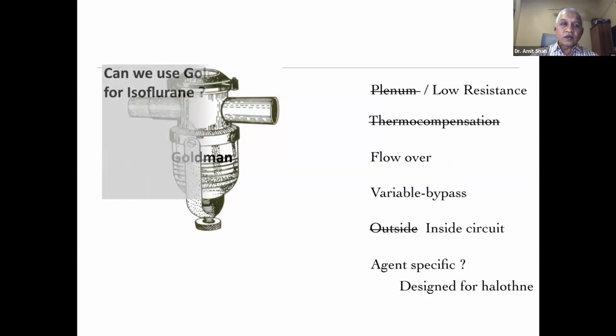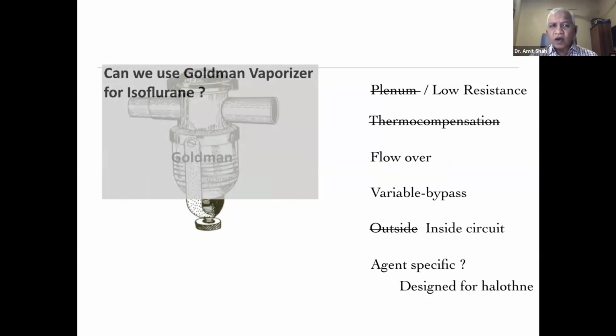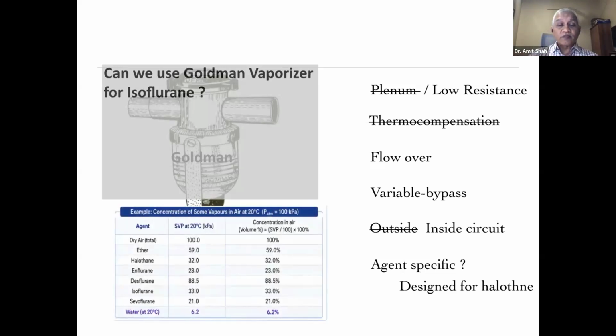Okay. So can we use it for isoflurane? Those who have worked in private practice in the older times, when we switched from halothane to isoflurane, some of them have used it. Now we'll understand the vapor pressure and why we can use it. The vapor pressure of halothane is 32, the vapor pressure of isoflurane is 33. So it generates a similar type of vapor. So when we put it on 1, it will deliver a concentration of 1% if we want it that way. Because the vapor pressure is the same, we can probably use isoflurane in the Goldman bottle.